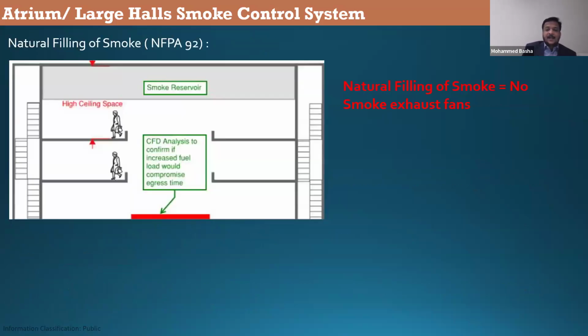So this is called natural filling of smoke, no exhaust. You can see the top space is called a smoke reservoir because when a fire develops, the smoke goes vertically up and hits the ceiling, then moves radially, then starts descending down. In this case, the space between the soffit, which is the top of the slab, and the top of the occupant is very small. It is not desirable to use such a system in an atrium. This is what I was explaining in the previous slide.